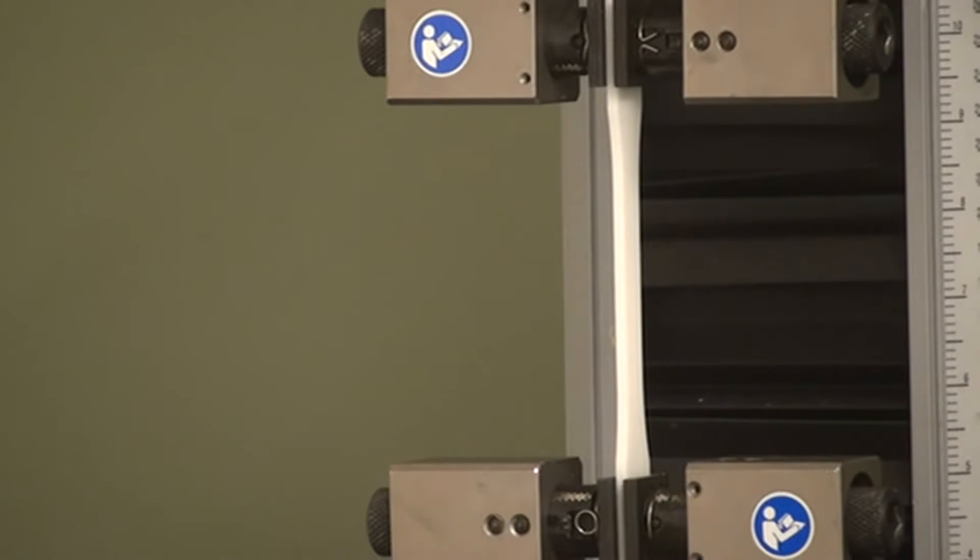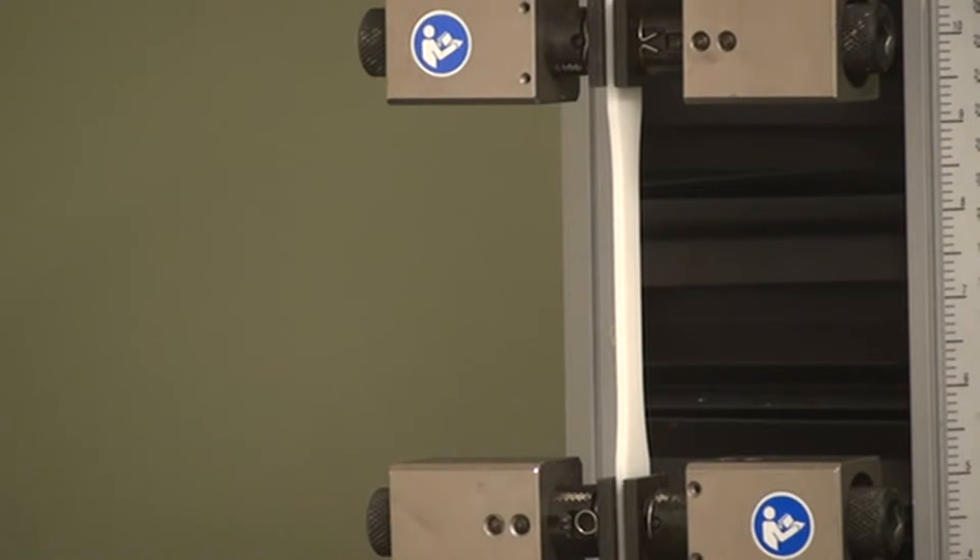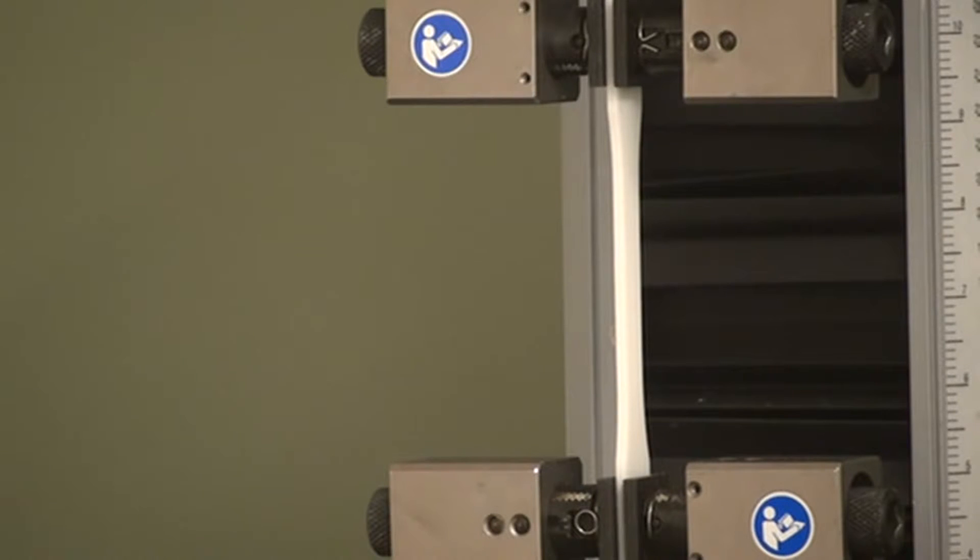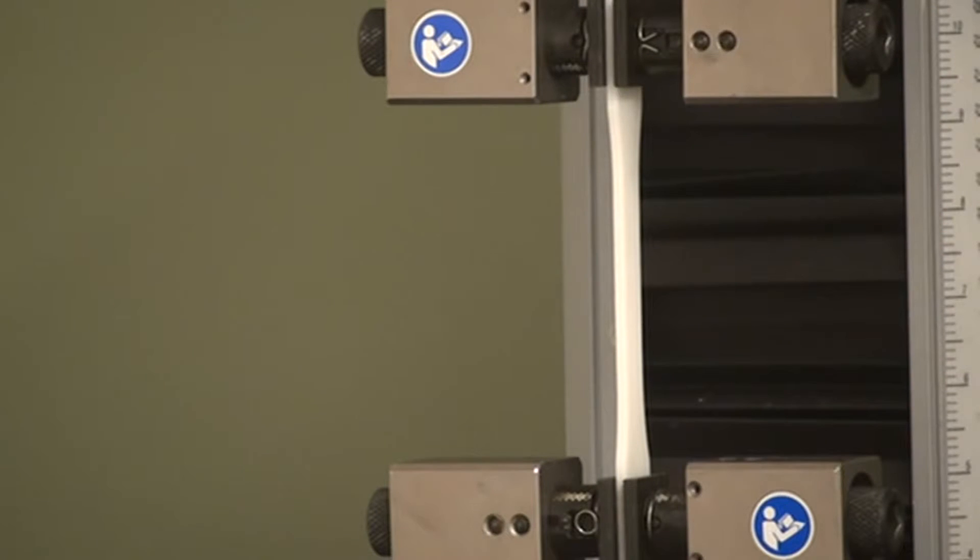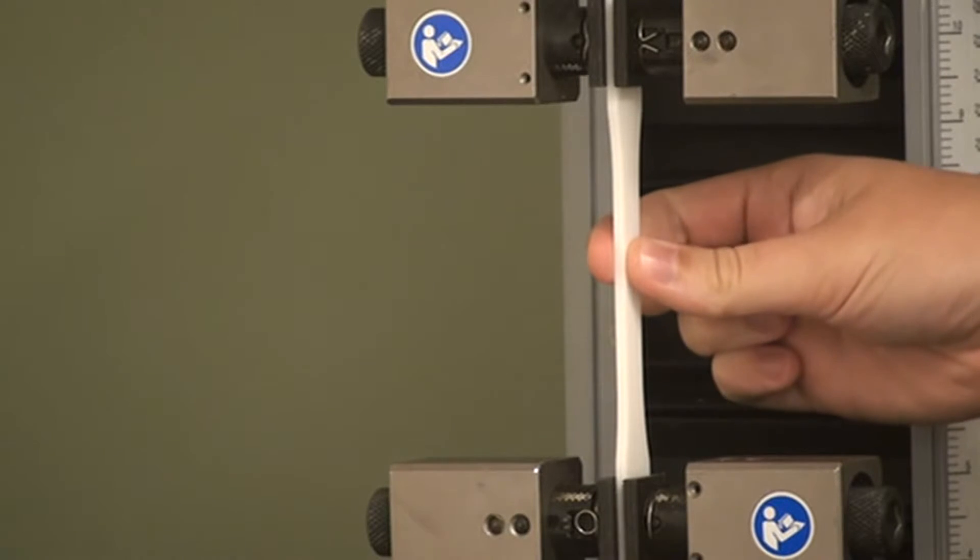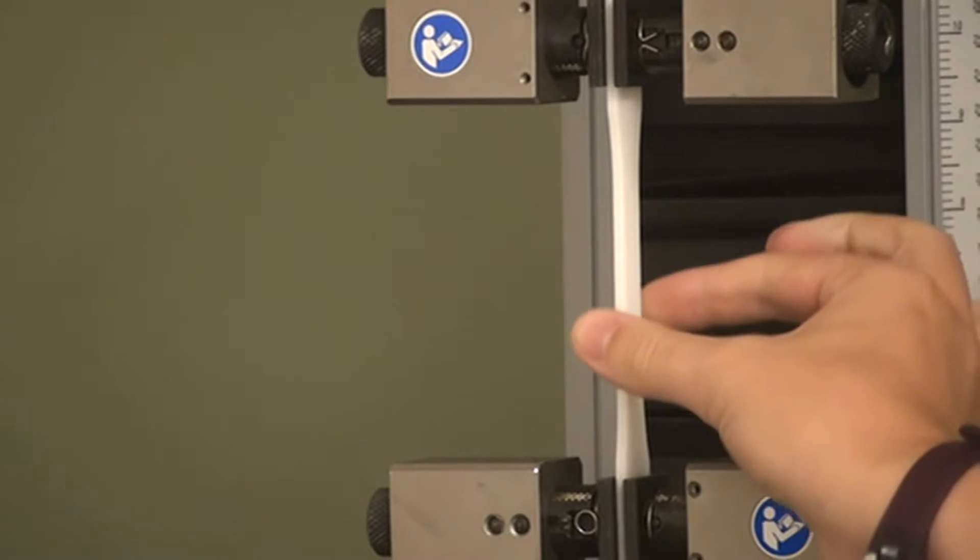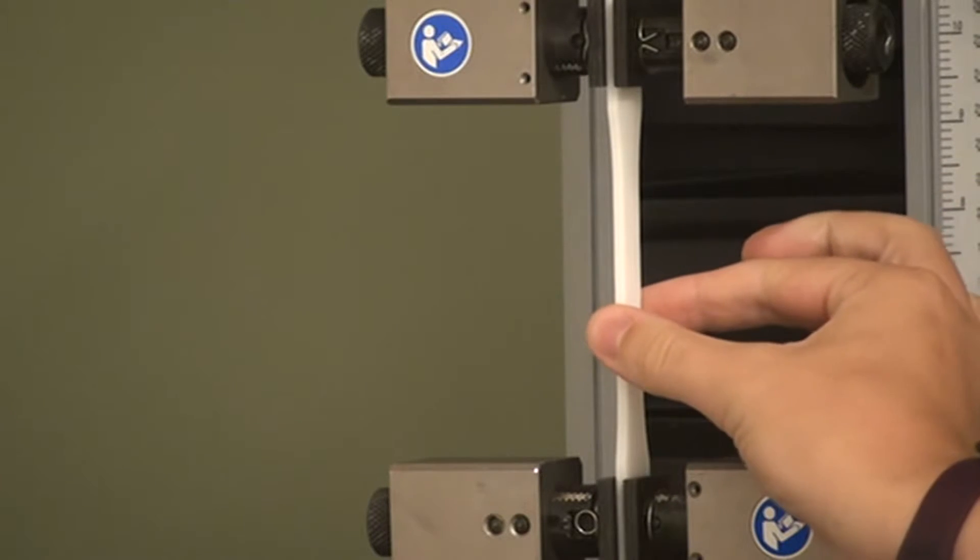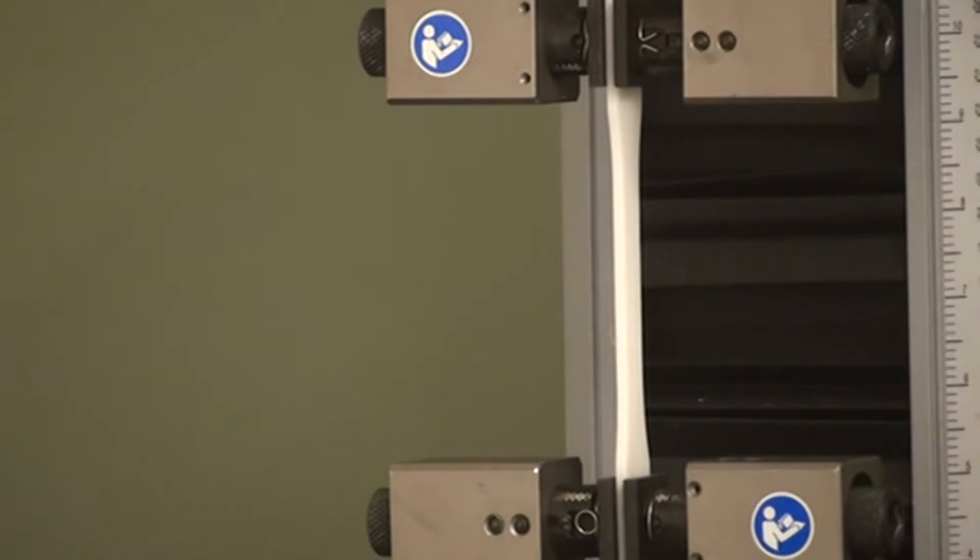After loading your sample but prior to testing, there are some important measurements that need to be made and inputted into the Blue Hill software. For rectangular samples like this piece of plastic or rectangular leather, the most important measurements to make are the thickness of the sample, the width of the sample, and the length of the sample.